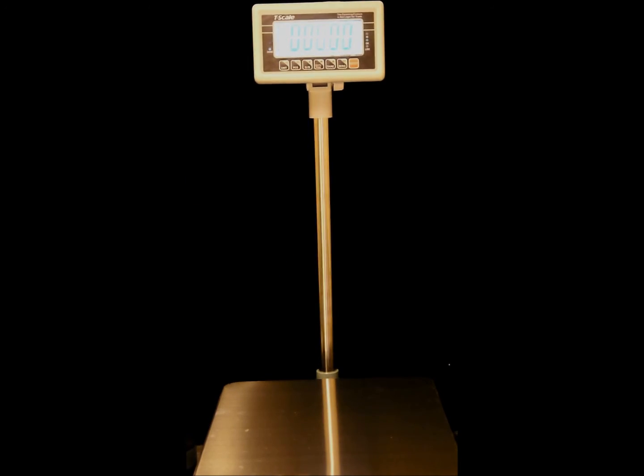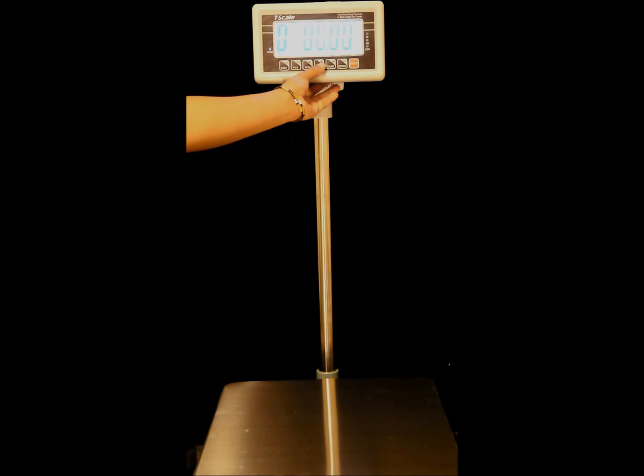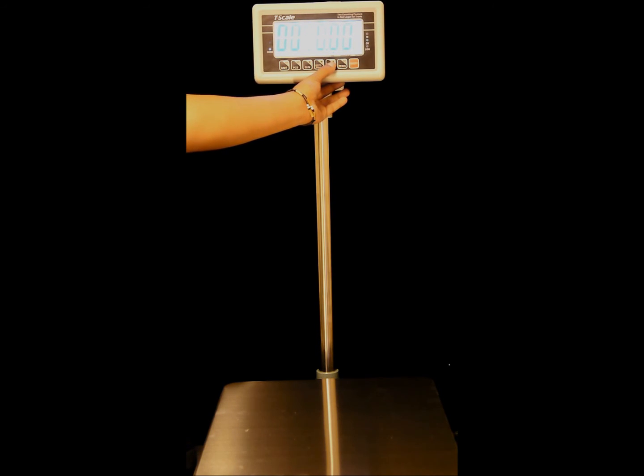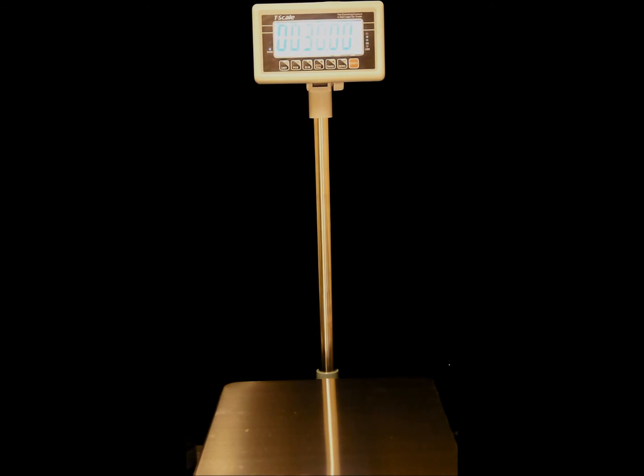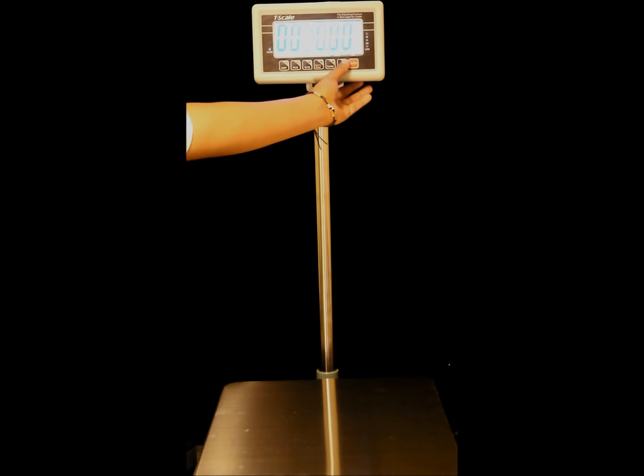Now we're going to enter in the calibration amount. We could use the gross net key to move to the left, or the print key to move to the right. Now we're going to press the tare key to increase the value of the flashing digit. We're going to be using 30 pounds to calibrate, so we're going to enter in 30, then we're going to press the zero key.